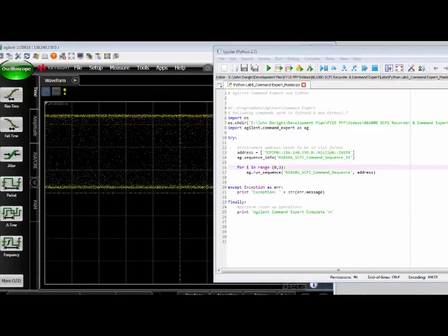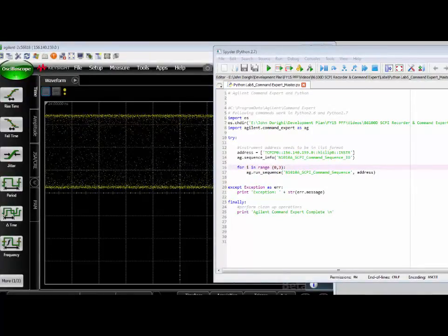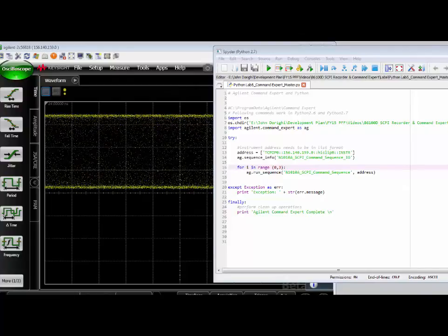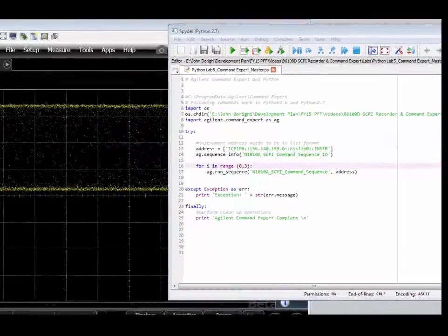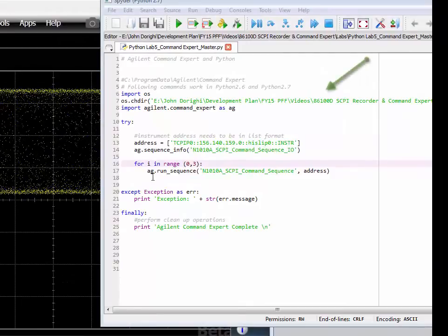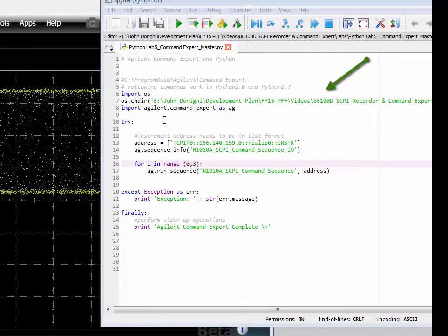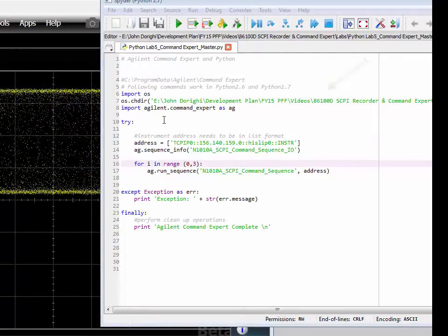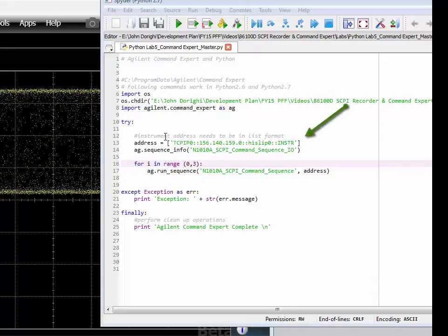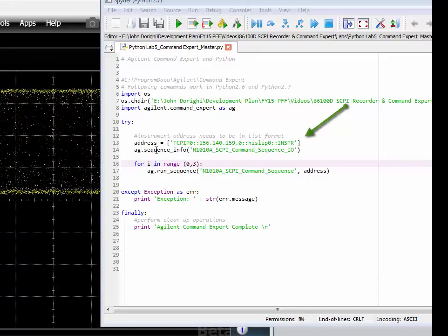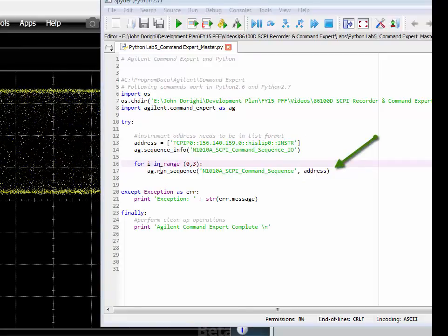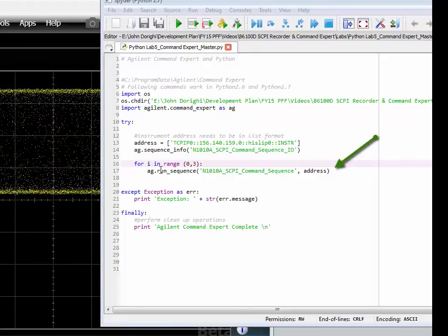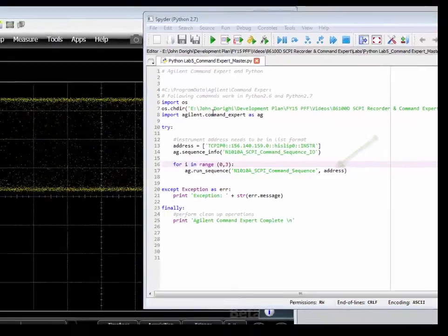I've opened up a Python development environment. I'm using the Spyder IDE from Anaconda. You can see it's a simple script. I just point the Python script to the directory where I've saved the Keysight Command Expert script. I provide an address for the instrument. I provide a name for the sequence that I'm going to run. In this case, I'm just going to loop on the sequence that I run three times and end the script.